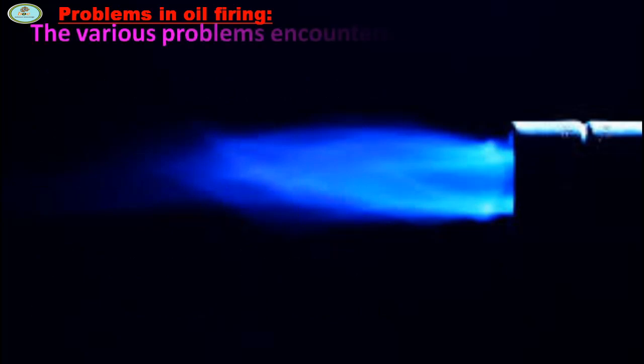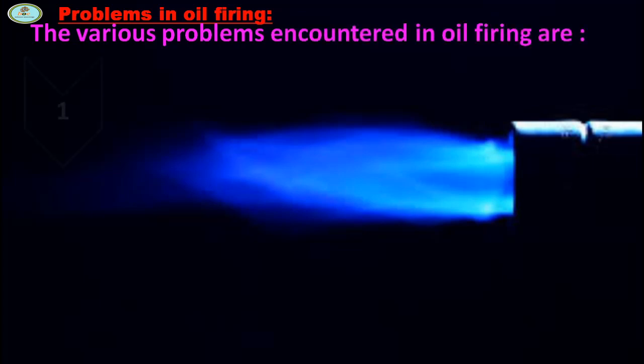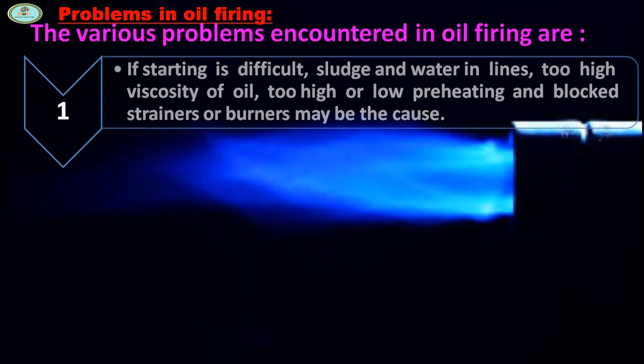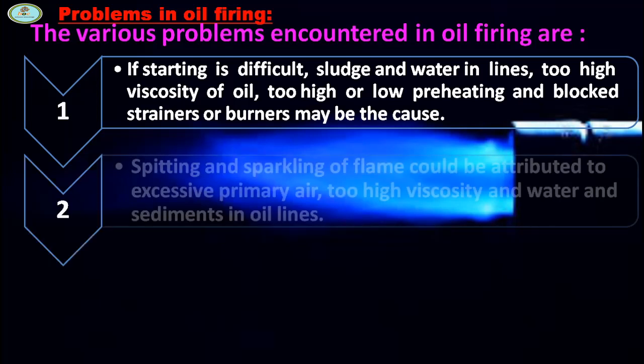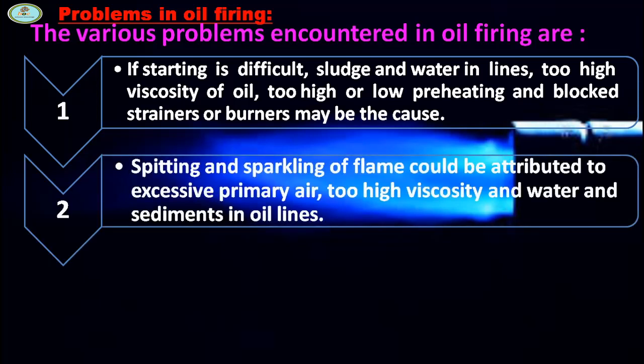The various problems encountered in oil firing are as follows. If starting is difficult, sludge and water in lines, too high viscosity of oil, too high or low pre-heating, and blocked strainer or burner may be the cause. Spitting and sparkling of flame could be attributed to excessive primary air, too high viscosity, and water and sediments in oil lines.